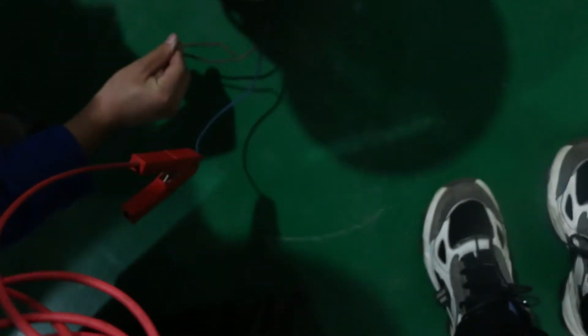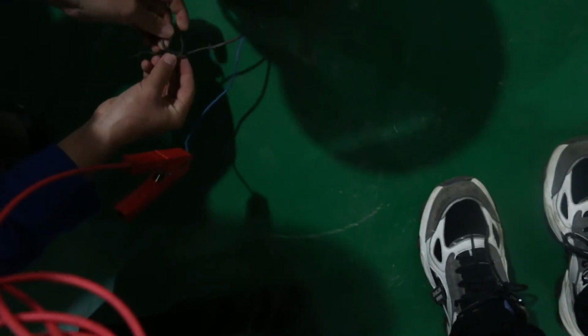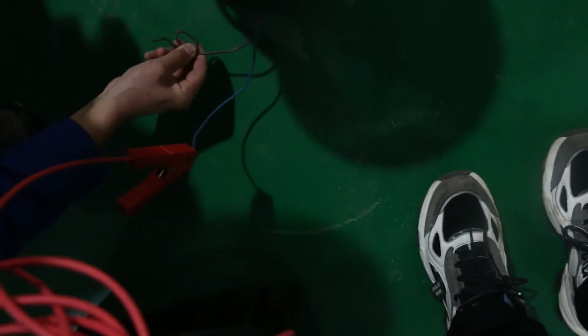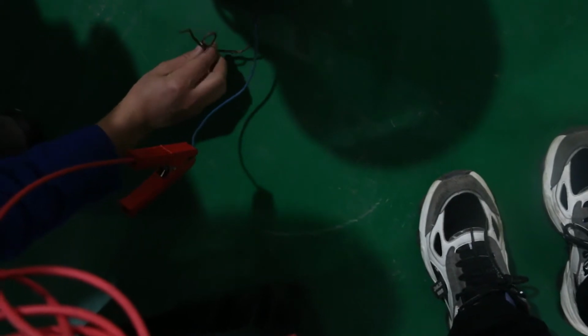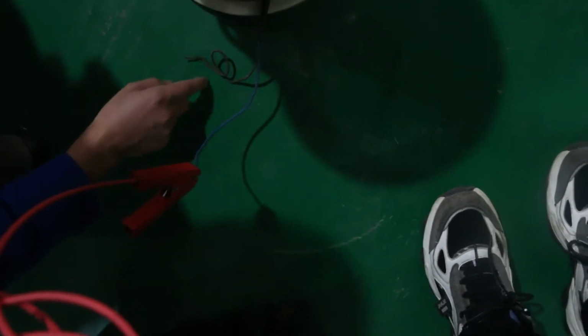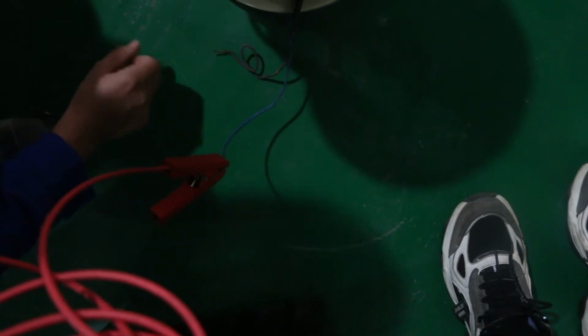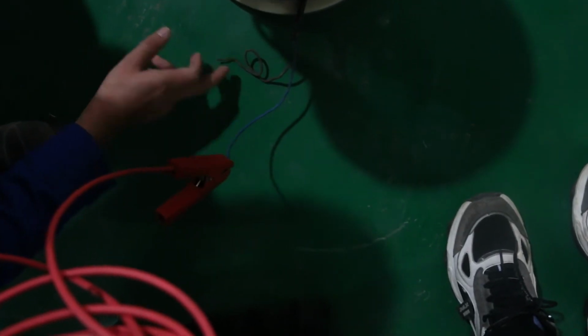Connect the other end of the high voltage output line to the faulty phase, and the other good phase is suspended. Because the ground for our experiment is insulated, we put it on the ground. The cable ends were connected together during rough testing, and now untied and suspended.